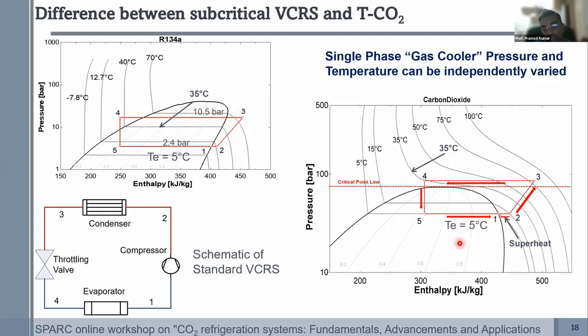Whereas in a transcritical cycle, you now have independent freedom to push this as high as you want. And then you can control the quantum of cooling by, we'll come shortly to it. But if you keep pushing higher and higher, it does have an effect on the quantum of cooling that you can get. And also in terms of heat pump, you can now go to much higher and higher temperature, because you're outside this dome, outside the critical point.